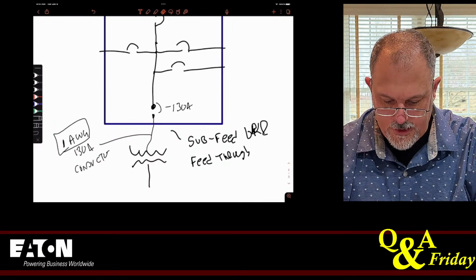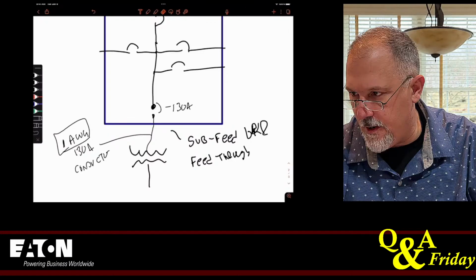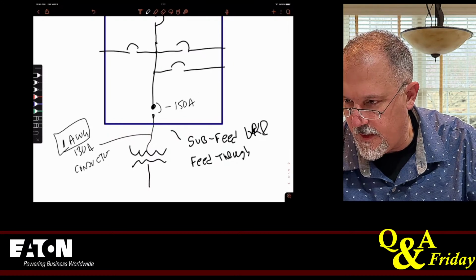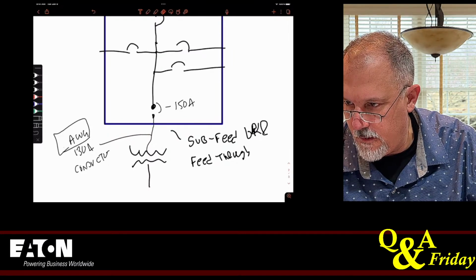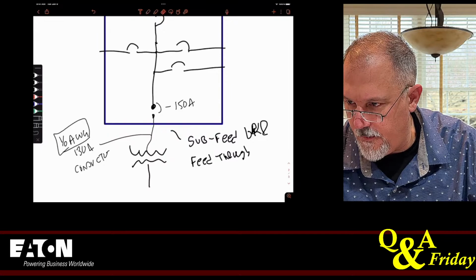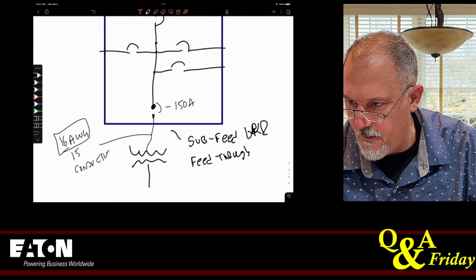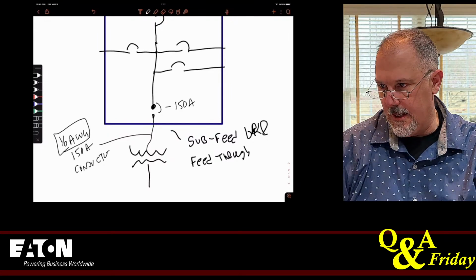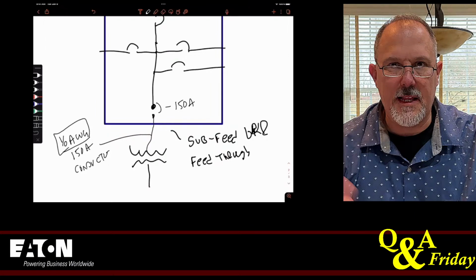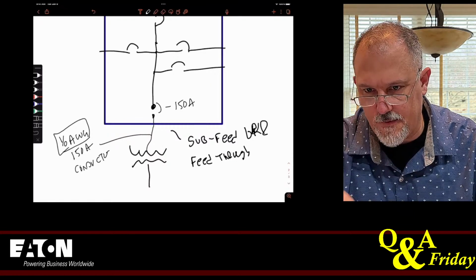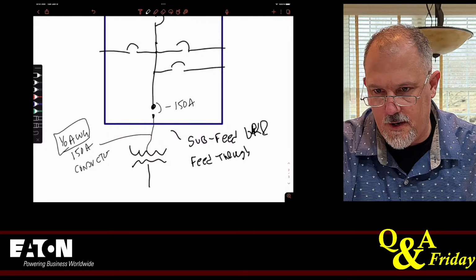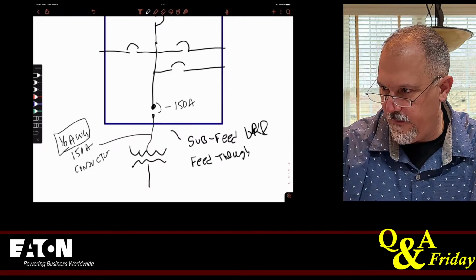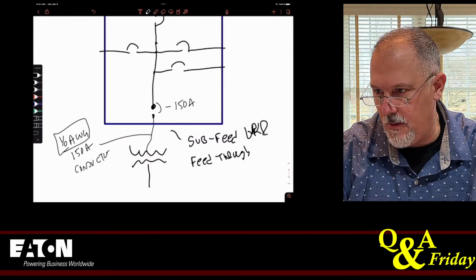Let's go back to our conductors again. Put a 1-aught in there. Make this 150. I'd feel more comfortable with that. A 1-aught, 150 amps worth of conductor. I think that smells better, don't you? What do you think, Jeff? Or Alan? Jeff's gone. Alan, I think that might be a little bit better. Put a 150 amp sub-feed breaker in that panel.